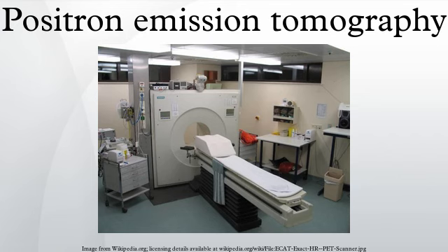Instead, the isotope must be prepared first, then afterward, the chemistry to prepare any organic radiotracer accomplished very quickly, in the short time before the isotope decays. Few hospitals and universities are capable of maintaining such systems, and most clinical PET is supported by third-party suppliers of radiotracers that can supply many sites simultaneously.